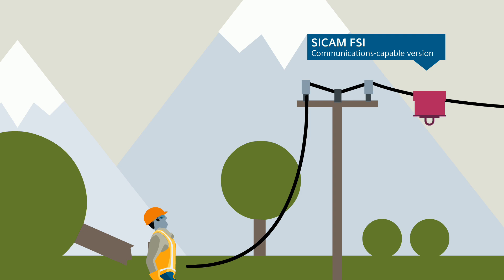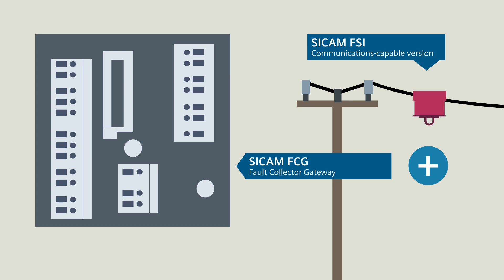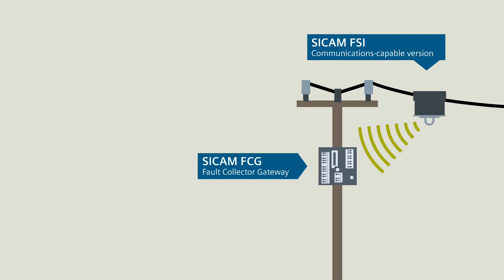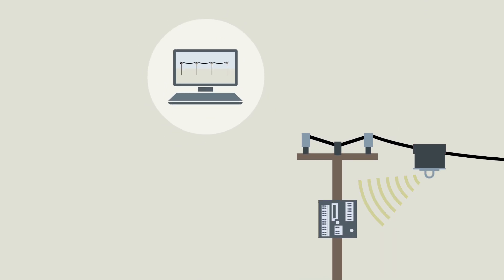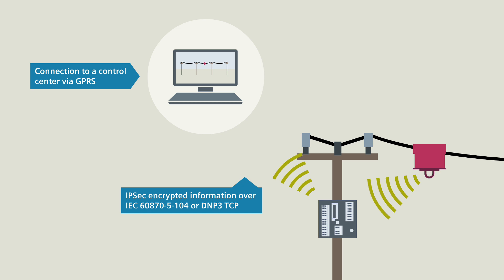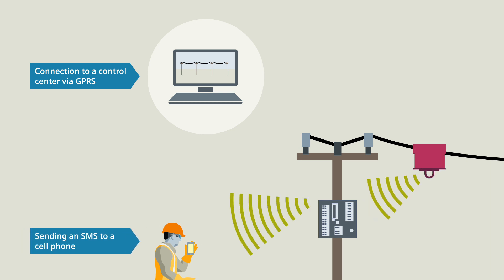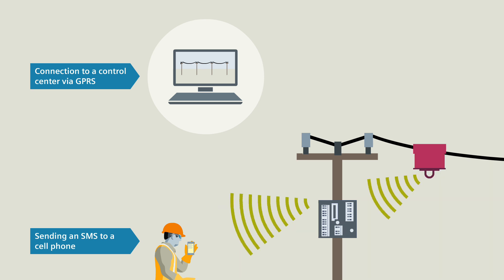Alternatively, you use the communications-capable version of the SICAM FSI in conjunction with a fault collector gateway SICAM FCG. With this solution, the SICAM FSI additionally sends fault information to the SICAM FCG via AES-128 encrypted short-range radio communication. The SICAM FCG then establishes a connection to a higher-level control center via GPRS and transmits the information IPsec encrypted over IEC-104 or DNP3-TCP. In addition, the SICAM FCG can also send an SMS directly to the cell phone of a service technician.